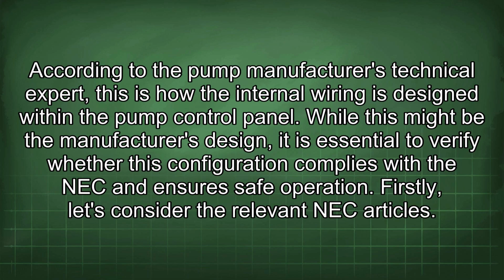According to the pump manufacturer's technical expert, this is how the internal wiring is designed within the pump control panel. While this might be the manufacturer's design, it is essential to verify whether this configuration complies with the NEC and ensures safe operation. Firstly, let's consider the relevant NEC articles.